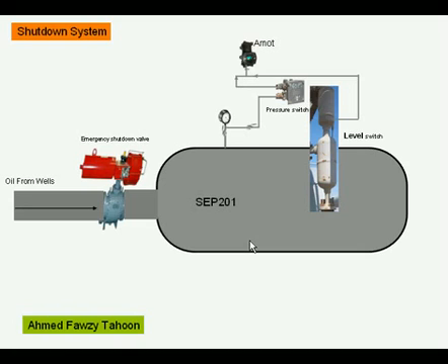The pressure switch is connected with the Amot and saves the Amot supply signal at normal pressure, and vents it at high pressure. The output signal of the Amot is transferred to the ESD to maintain the ESD open.